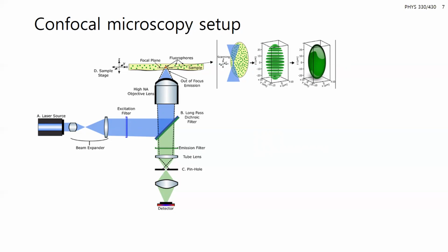You're going to pass that excitation source to an objective on a microscope, where this dichroic filter is a special type of mirror that will reflect shorter wavelengths and allow longer wavelengths to pass through. The important thing with confocal microscopes is you overfill the back of the objective. So then you tightly focus your laser light to a single point. That's diffraction limited here, with that 250 nanometers. So that's what this light blue is representing here.